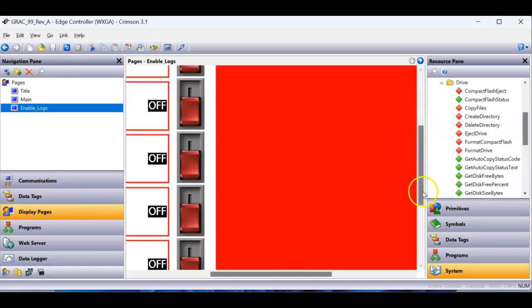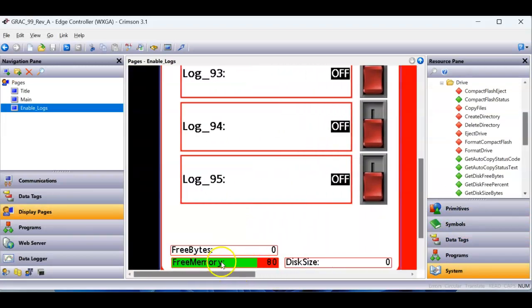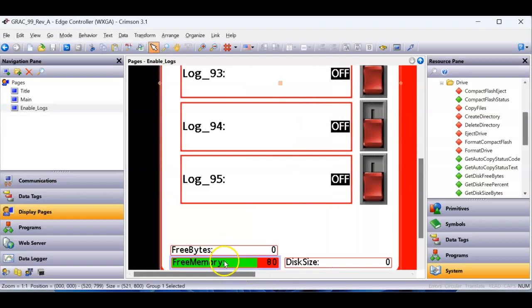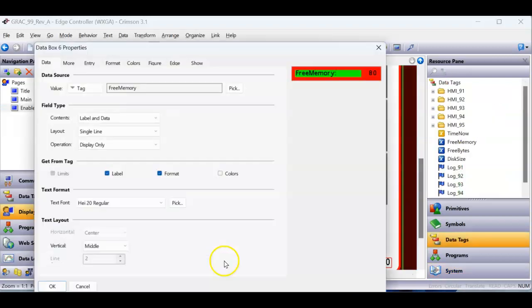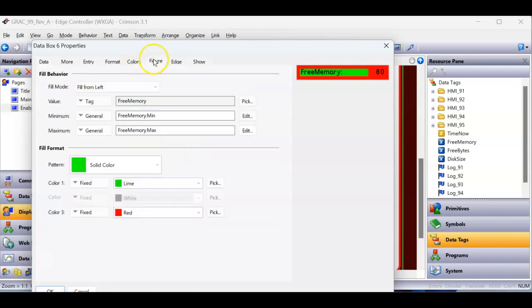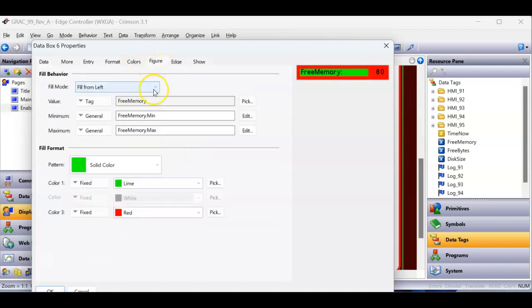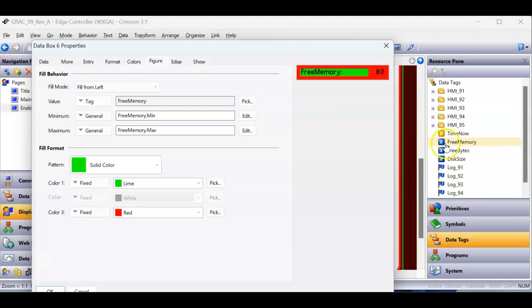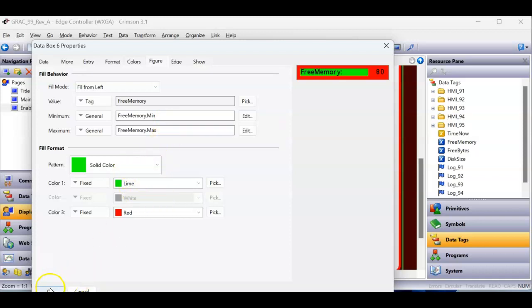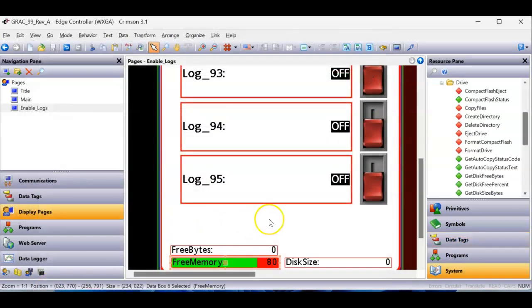Let me zoom in so you guys can see this a little better. If I double-click on this free memory one, double-click on it. If I go to the figure tab, on the figure tab, normally there's block mode here, I chose fill from left, and then I simply drag the free memory tag into here. The dot min and max here is the 0 to 100. That's what it's doing there, and then this is where I give it the coloring. So that's how it has that on there.